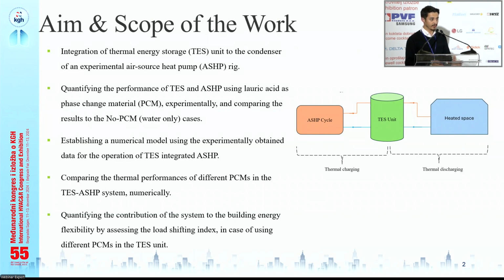And first, we try to store heat by operating the heat pump, and then we use the pre-stored heat without actually operating the heat pump. The aim is shifting the loads from on-peak to off-peak periods, because we always emphasize electrification of the heating system. However, when we do this, it doesn't matter whether with fossil fuels or renewable sources, we push the electric grid a lot of load. That's why we need to reduce this. In order to reduce this, we need to shift it to the off-peak periods.